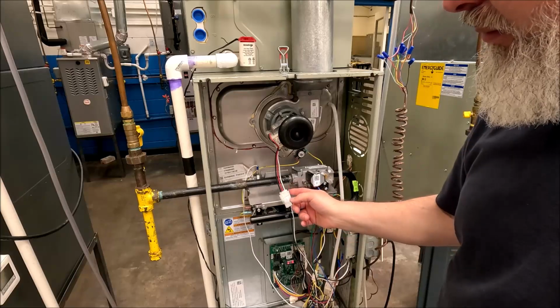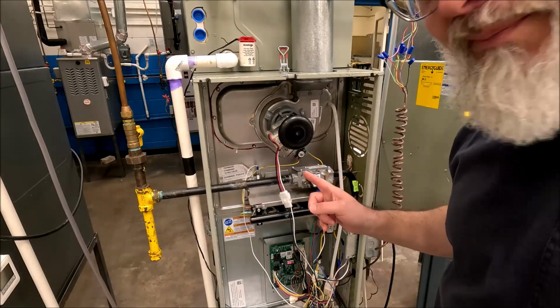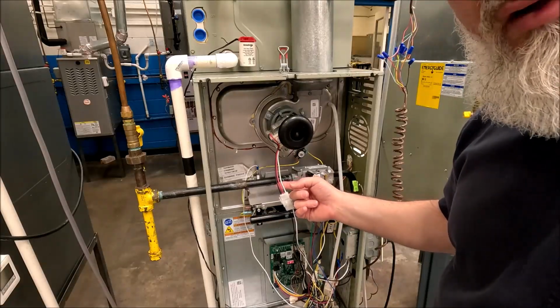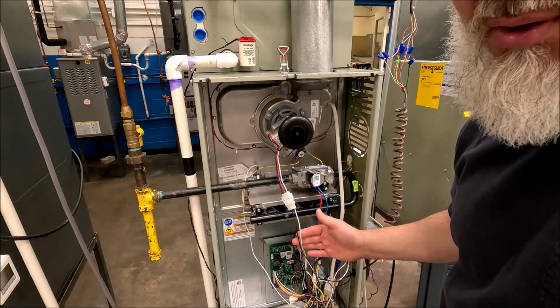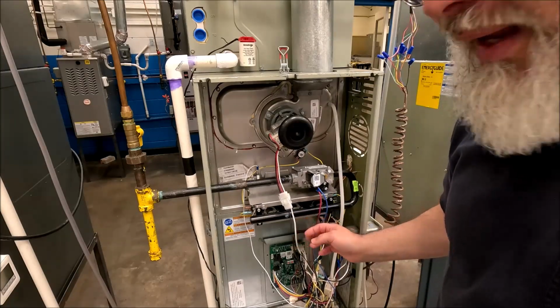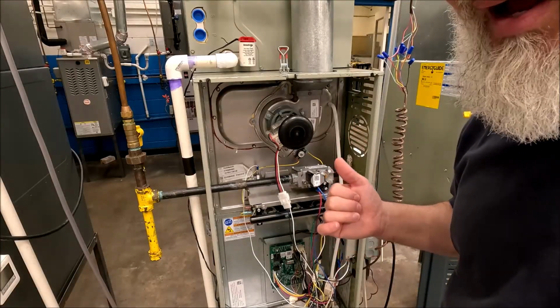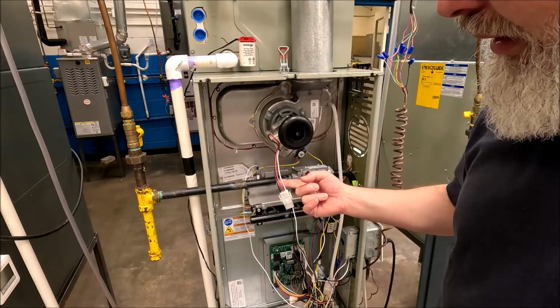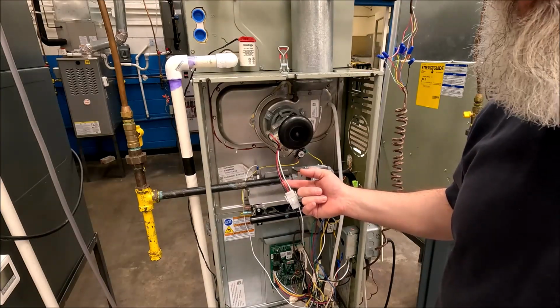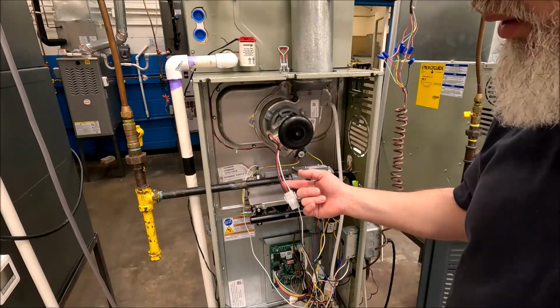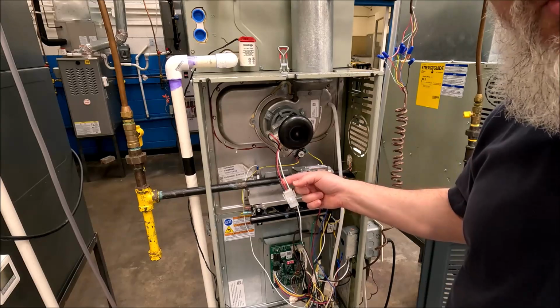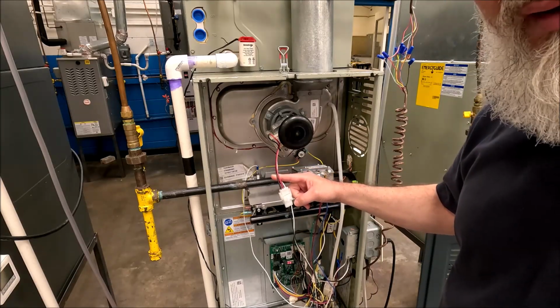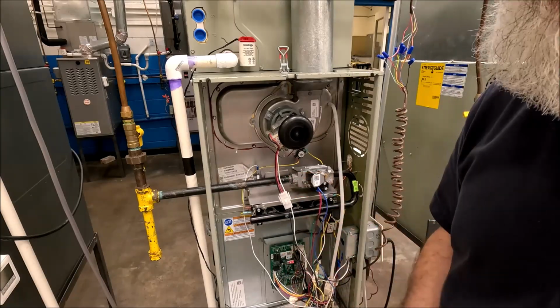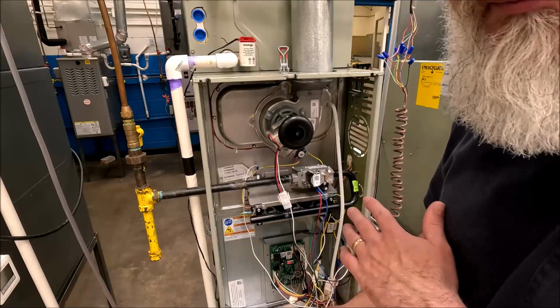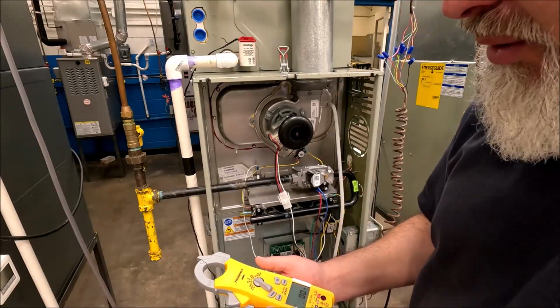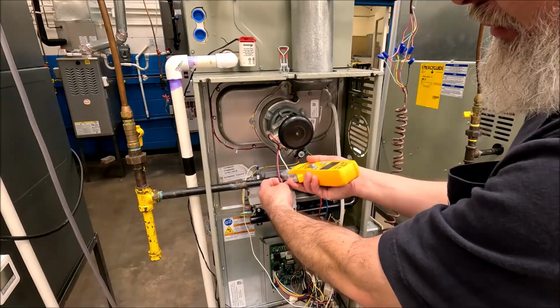But something that's different about this one is it's a 2-speed inducer motor on the motor side of the plug. Now the plug going to it is just 120 volts. It's got an L1 and a neutral. And if I'm dealing with a 120 volt load, I always check the neutral, because in the case of a 2-speed motor, what if they were both wired to run, low stage and high stage in this furnace, or whatever the situation is? No matter which one I'm using, low or high, which is the red and the black wires, I'm always using the neutral. That is always the other side. So anytime I'm in a 120 volt situation, neutral's the way to go. So I would, got a brand new meter here, I would check the white wire.